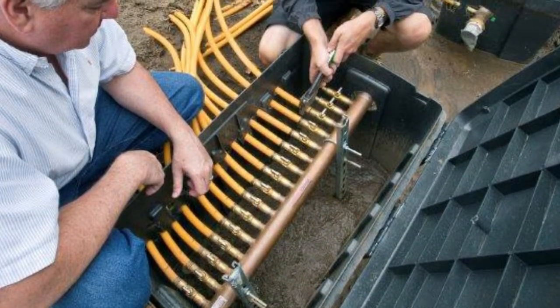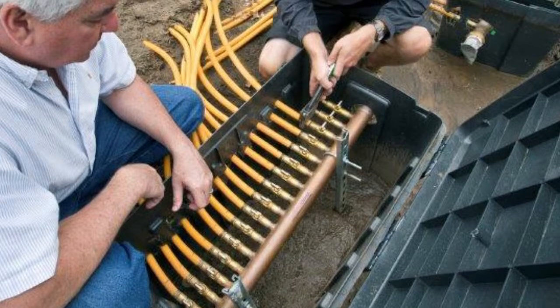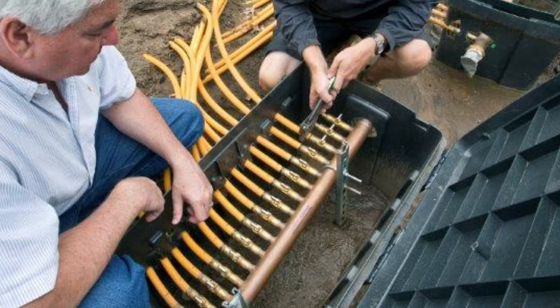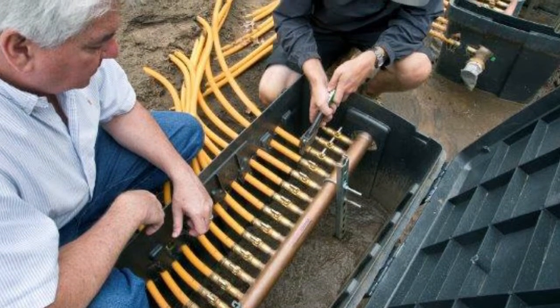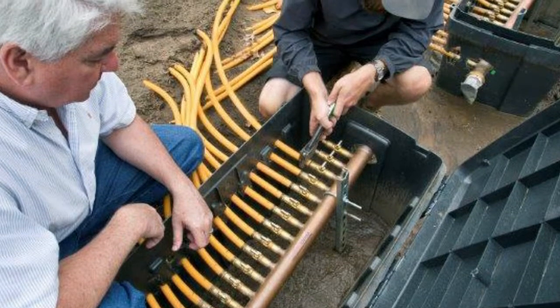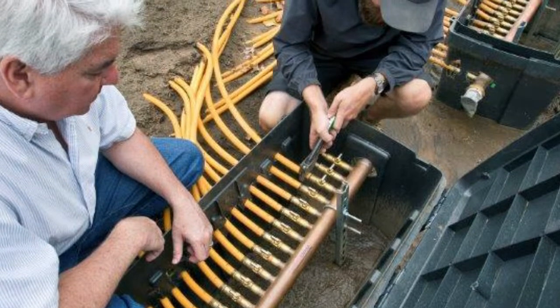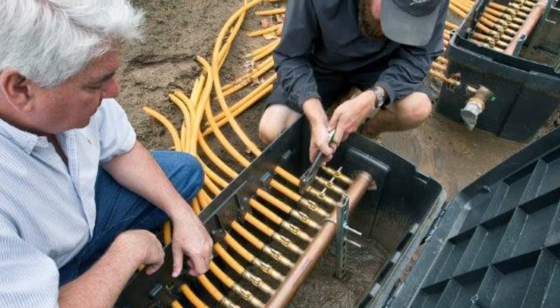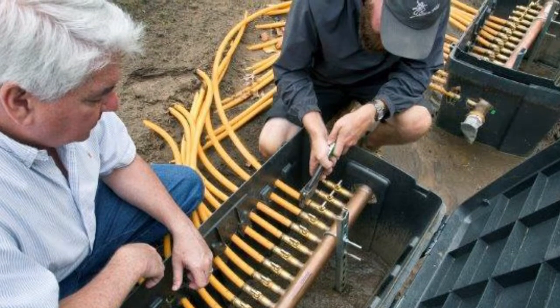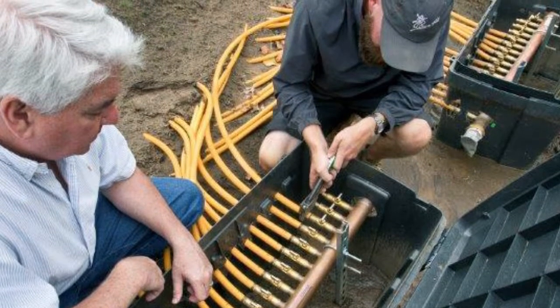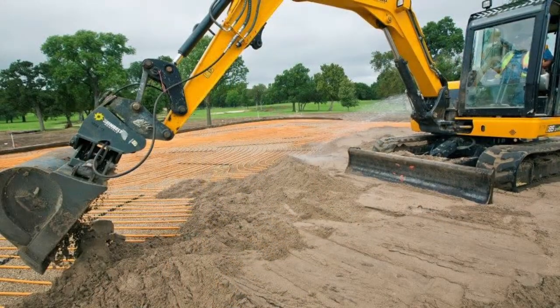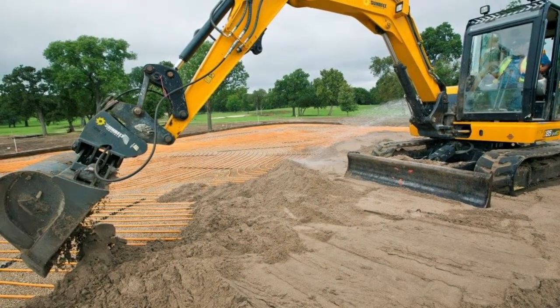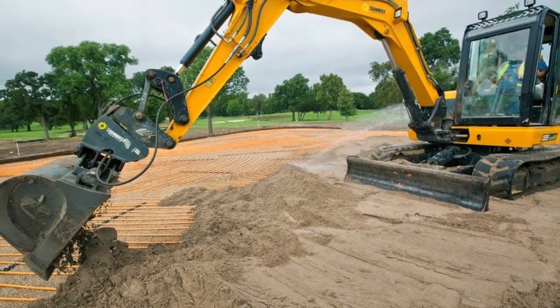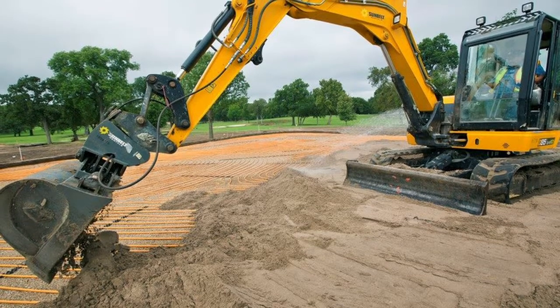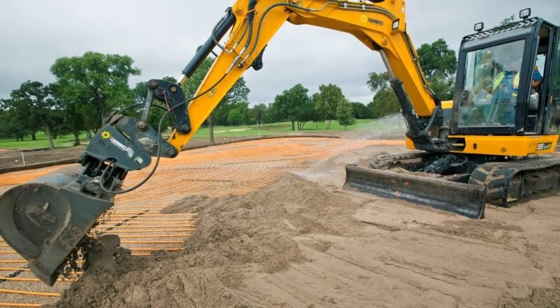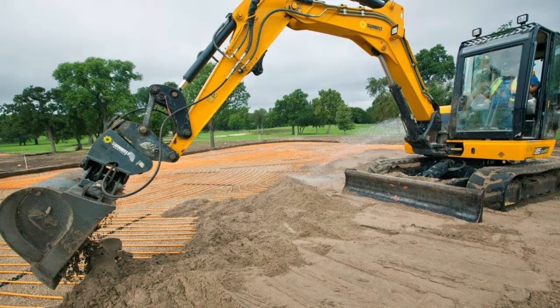The main difference between this project and a normal air-to-water heat pump application was having to pump water long distances to any given green. A low-pressure system was needed, but hot or cold water still needed to be pumped economically through 9,000 linear feet of tubing. The biggest logistical consideration with heat pumps was the challenge for three-phase power at each of the 24 greens and practice surfaces. The challenge was to see if a few large custom heat pumps could serve numerous greens.